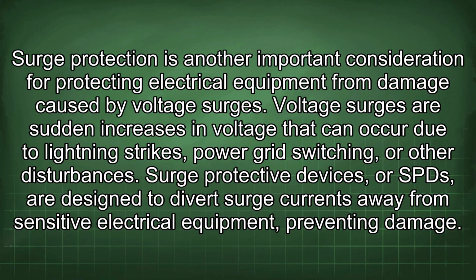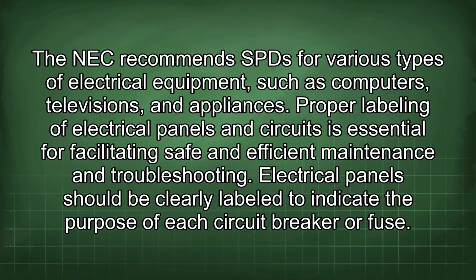Surge protection is another important consideration for protecting electrical equipment from damage caused by voltage surges. Voltage surges are sudden increases in voltage that can occur due to lightning strikes, power grid switching, or other disturbances. Surge protective devices, or SPDs, are designed to divert surge currents away from sensitive electrical equipment, preventing damage. The NEC recommends SPDs for various types of electrical equipment such as computers, televisions, and appliances.